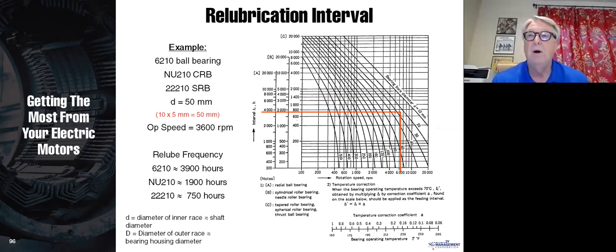However, if the motor really runs hot, in many cases, it's not going to be the insulation that's going to fail first. It's going to be the bearing. And so when the bearing fails, a lot of times the grease gets too hot, it runs out, doesn't have proper lubrication, and we end up with just more friction in there, and the bearing gets hotter, and then more oil runs out, more friction, and that causes it to get even hotter, and pretty soon you end up with vibration in that bearing or noise in the bearing, and of course by that time it's a little too late. But those are typically the places where you're going to see high temperature failures on a motor, either in the insulation or in the bearings.